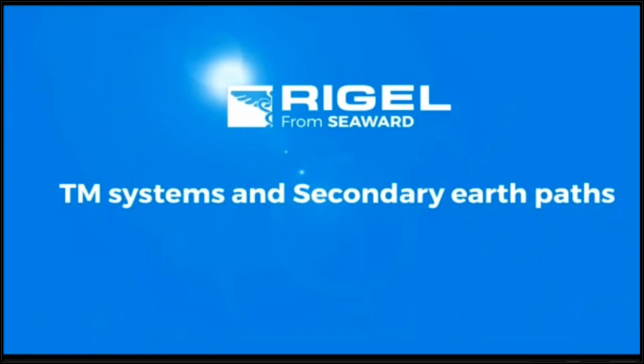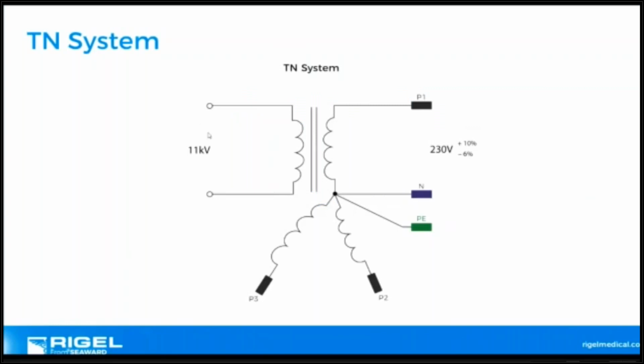TN systems and secondary earth paths. TN system, this comes from the substation. This is our 3 phases. We have phase 1, phase 2, and phase 3. At the substation, these are connected, neutral and protective earth connected together. This is only applicable for various parts of the world. They also have 110 volts in many places.